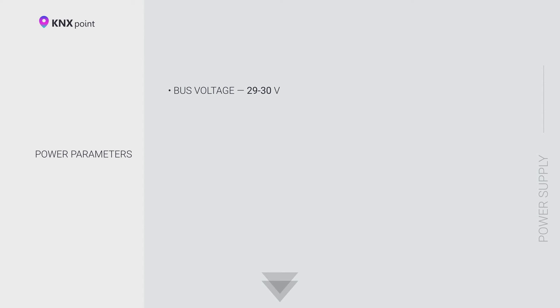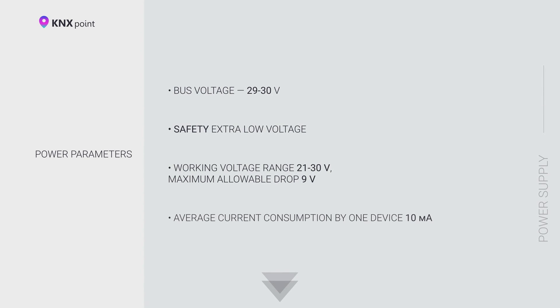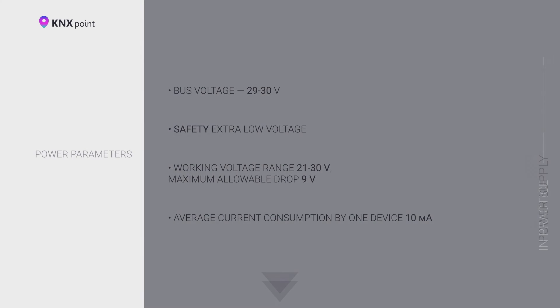The standard installation power supply for an installation of more than 32 devices has a capacity of 640 mA. However, you must understand that some devices may consume more than the standard 10 mA and you will have to install an additional power supply or divide the line into segments. Power supplies with the power of 160 and 320 mA are enough for small apartment projects where there are not so many KNX devices.